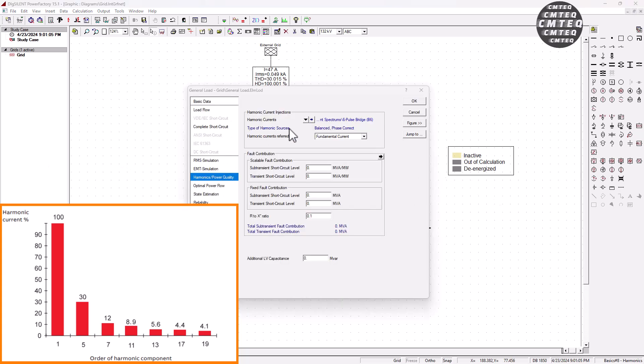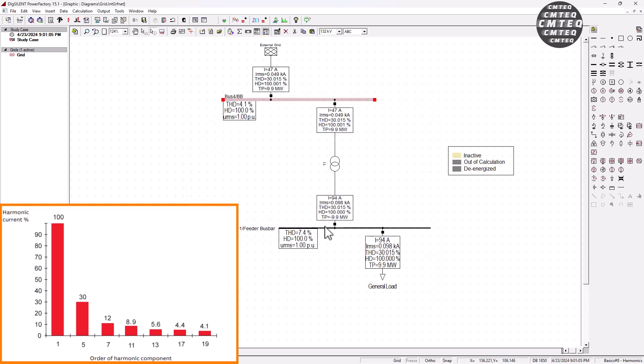The second point is that in our harmonics analysis, we take the harmonic currents and refer them to fundamental currents. The harmonic currents depend on the impedance at harmonic frequency. When the generator's impedance increases, it creates a larger voltage drop across the network for these harmonic currents, which basically amplifies the harmonic voltage at the particular point, as we've seen at these bus bars. On the other hand, lowering the generator's impedance — basically a higher short circuit current — allows fewer harmonic voltages to develop, keeping the THD lower.